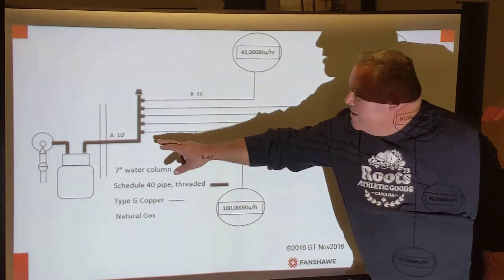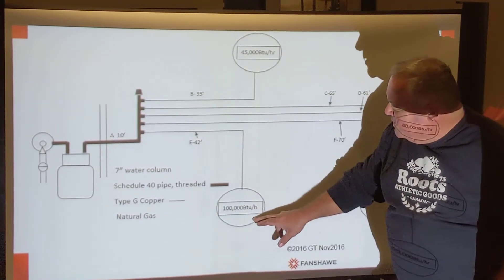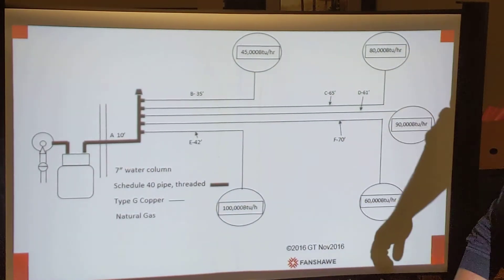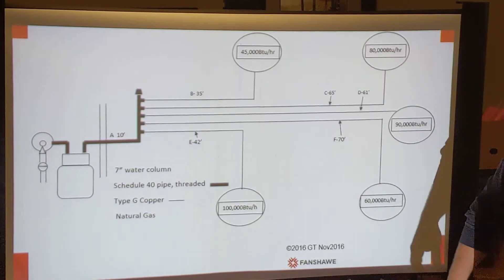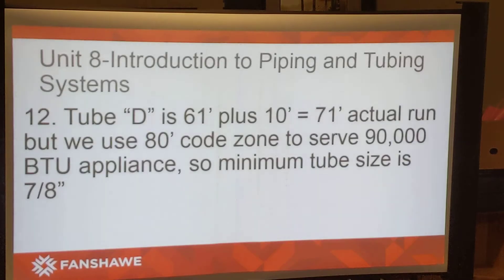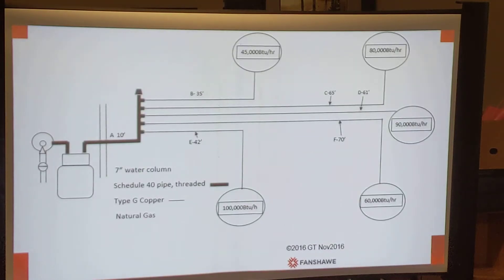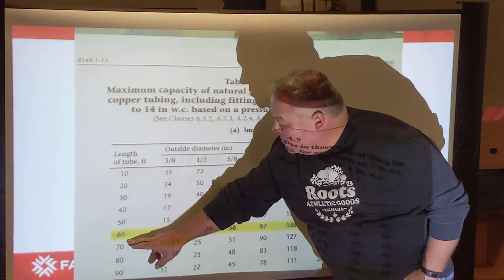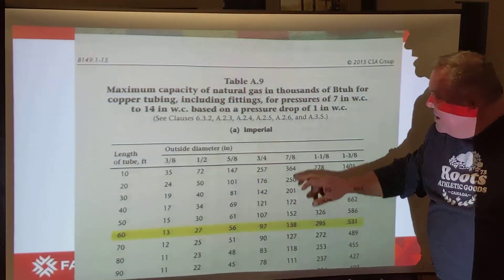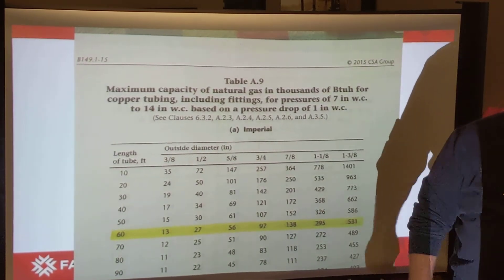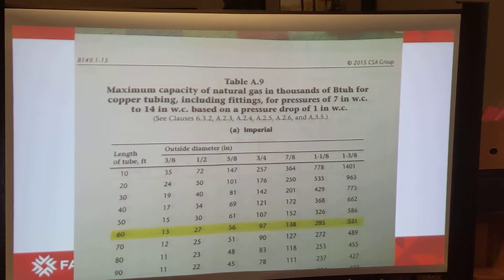For section E, we have 42 feet of tubing with 100,000 BTUs per hour along with the 10 feet of schedule 40 pipe, so 42 plus 10 is 52 feet, which takes us to the 60-foot code zone. At the 60-foot code zone looking for 100,000 BTUs, three-quarter inch falls just short, so the answer is 7/8-inch tubing.